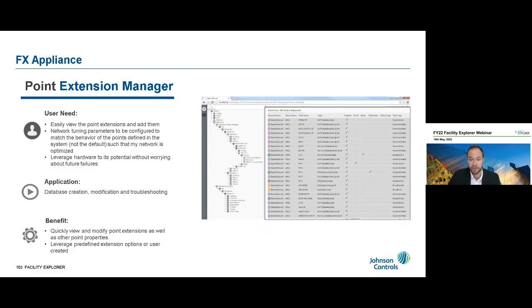This also shows how we can view and change tuning policies from the Extension Manager, setting how frequently points try to communicate on the network so we can manage network traffic, reduce interference, and build a stable system. There's a lot of flexibility with the Point Extension Manager — it's a huge time saver compared to the manual way. If you're familiar with Niagara, you'd have to find each point in the nav file and manually add a trend or alarm, which takes time. This is a much easier and quicker way to do it.